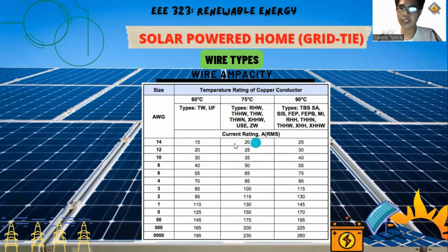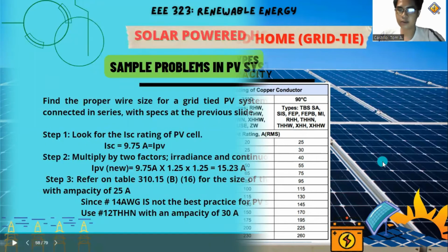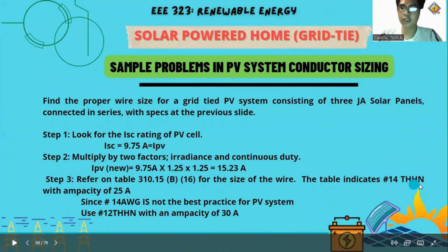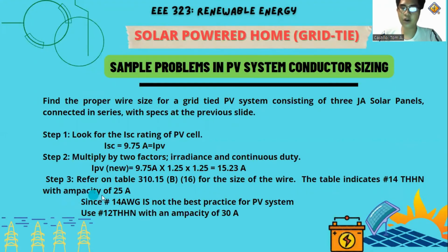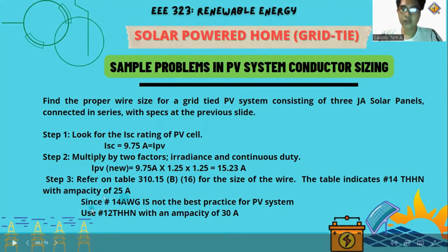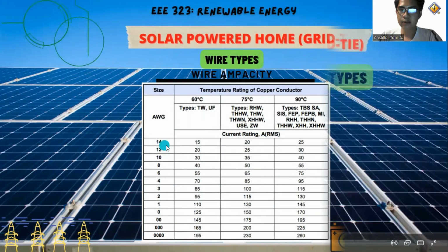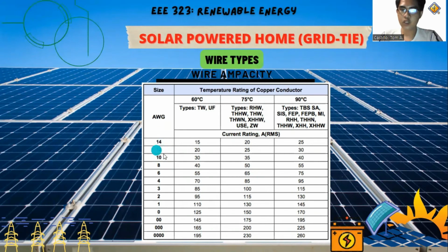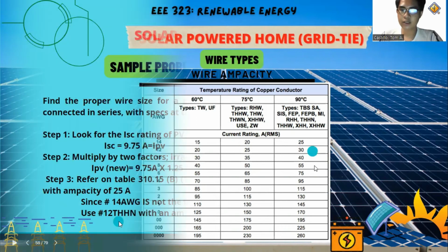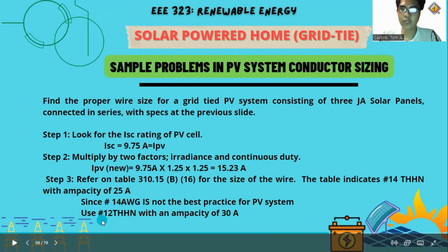So, bali, ang magiging size natin is 14. The table indicates number 14 THHN with ampacity of 25 amperes. So since number 14 AWG is not the best practice for PV system, kailangan natin tabaan yung wire natin. So ano ba yung kasunod ng number 14? So ang kasunod na number 14 is 12. So bali ang magiging ampacity na natin is 30. Kaya ang sabi dito, use number 12 THHN with an ampacity of 30 amperes.